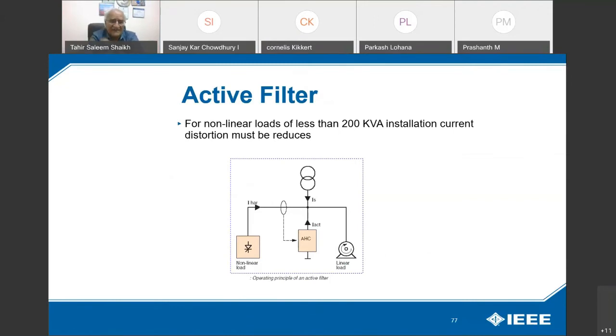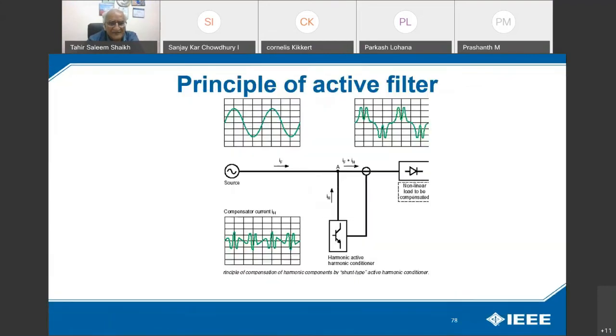The principle is simple: a nonlinear load generates harmonics, whether third, fifth, seventh, 11th, whatever it may be. These are countered in opposite phase; this harmonic generation unit creates a harmonic level which nullifies the impact of the one phase and the second and cross phase, and gives a simple, noise-free sinusoidal waveform to the linear loads. So this is called an active filter or sine filter. This is very expensive. These are the simple waveforms over here.